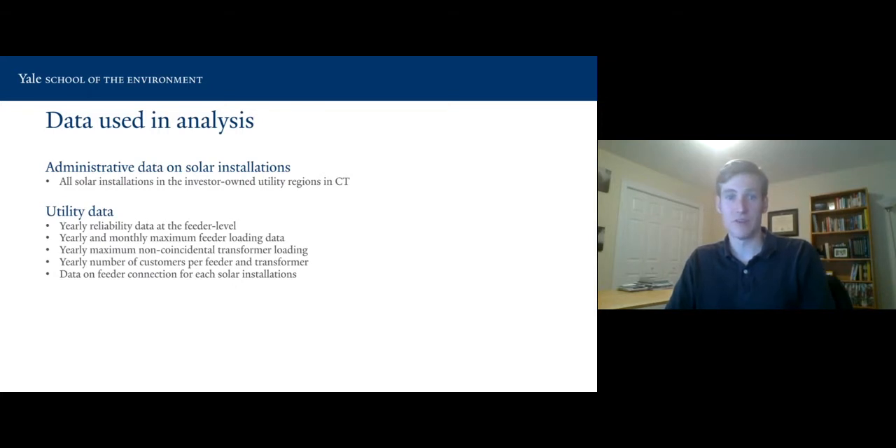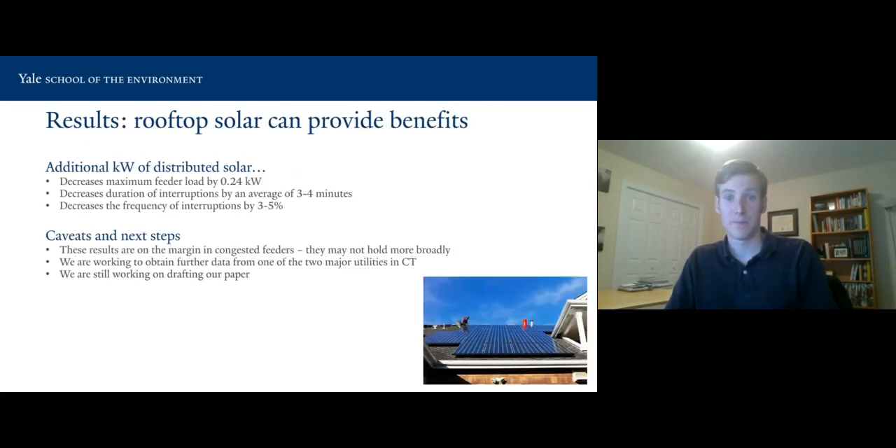The data used include administrative data on all solar installations, as well as utility data on a whole set of grid metrics important for the cost of upgrading and maintaining the utility distribution system. Our main results are that rooftop solar can indeed provide benefits: an additional kilowatt of distributed solar decreases the maximum feeder load by 0.24 kilowatts, decreases the duration of interruptions by an average of three to four minutes, and decreases the frequency of interruptions by three to five percent. Solar is cutting peak load, which is very useful, since during peak times when everyone is running everything, solar also happens to be running.